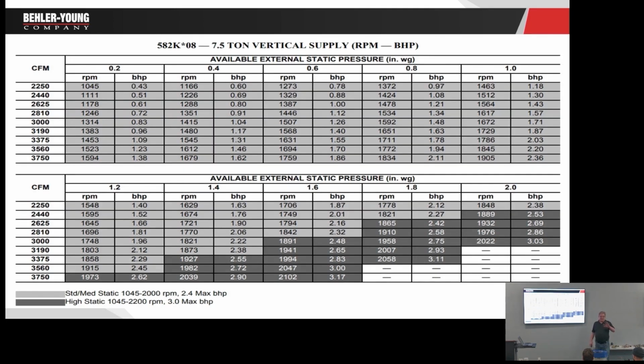Any questions on that so far? All right. So when we talk about static, like I said, residential, usually 0.5 is our design. Commercial, we could be 1 to 2 inches, which is pretty typical. So when we look at a medium static, or standard, medium, and high, that's how units are ordered. It has to do with the blower.